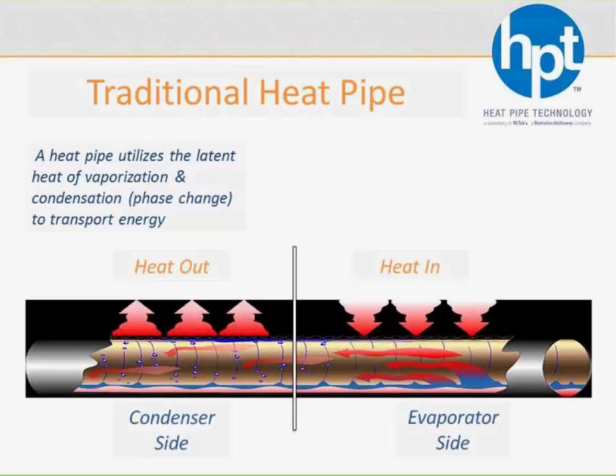So here's your traditional heat pipe. It doesn't require any power. It just requires a delta T, and that delta T is going to make it work. And basically, you put this tube with refrigerant in it, and you apply heat to one side. That refrigerant is going to pick up the heat. That refrigerant is going to boil. It's going to go to the open area, which is the other end, which is now cooler. It's going to give off that heat, condense back to a liquid, and it's just going to keep going back and forth, phase changing and transferring heat from one end to the other. Again, with no power, no moving parts necessary.